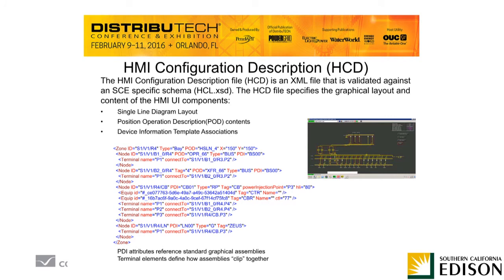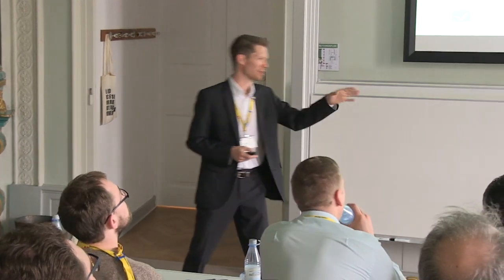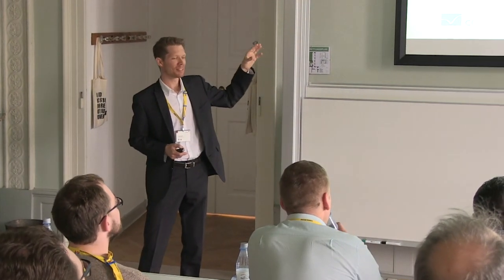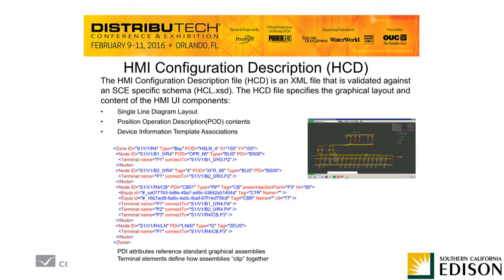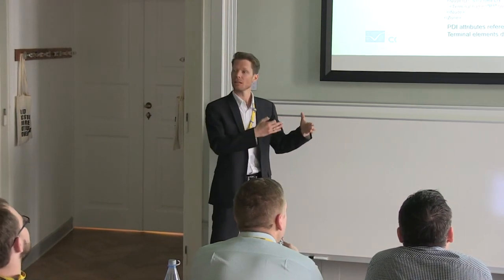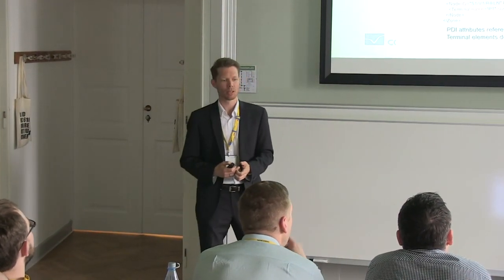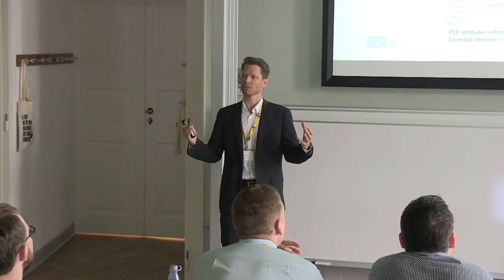Where does this come from? I put this slide in because normally Alex always asks me if I know about Southern California Edison, who did that already. Now it's already there, so you cannot ask me. This is a slide from Southern California Edison about automatic HMI configuration. So they did that already by means of SCL. They just extended it for their purposes. It's not normative what they are doing, but it's machine- and human-readable XML files which they just import and create their HMI at the substation. Bang.